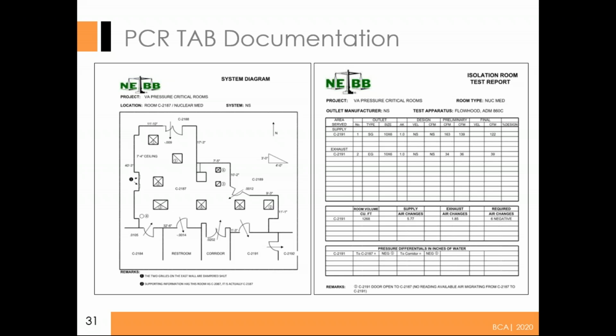Typically exhaust fans, each group or individual isolation room is going to have its own exhaust. Sometimes they're HEPA filtered. You just really need to understand your design of your system as a balancer for filter loading, especially on exhaust. Coming up with that design pressure, static pressure control for your exhaust. As filters load up, airflow goes down. So it's very important to understand how those systems are working, whether, once again, be the positive room or a negative room, especially when we have HEPA filters in those spaces.